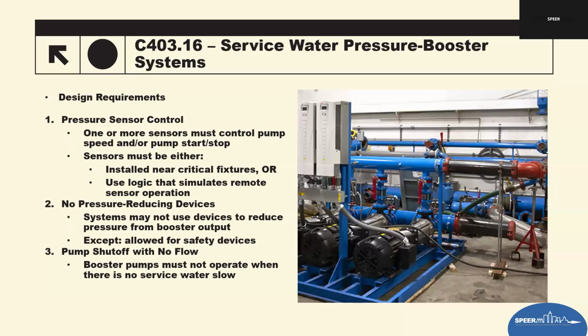So we've got pressure sensor controls. That's your first requirement. You've got no pressure reducing devices after booster pumps. Then you've got no pump operation when there is no flow. Those booster pumps must not run when the service water is not flowing. This provides protection against unnecessary energy use, overheating, pump wear, and wasted water. The system should include no-flow detection. The purpose of that is to prevent, again, energy waste, ensuring properly sized pumps and improving longevity of pressure booster systems.